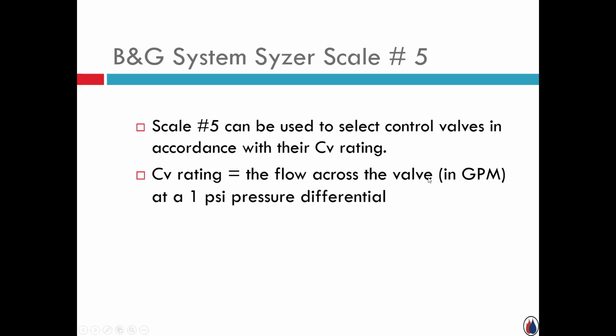And whenever you look at a published information submittal, whatever, of a valve, and it lists the CV, what it's telling you is this. That valve was tested. The flow across the valve stated in GPM that creates a 1 pound pressure drop across that valve becomes that manufacturer, that valve's CV rating, C sub V rating. So if I have a rating of 50 on a particular valve, what it's saying is the manufacturer tested it and had to move 50 gallons a minute through the orifice to create a 1 pound pressure drop. And that becomes, bang, that's a CV. 50 gallons a minute, 1 pound pressure drop.